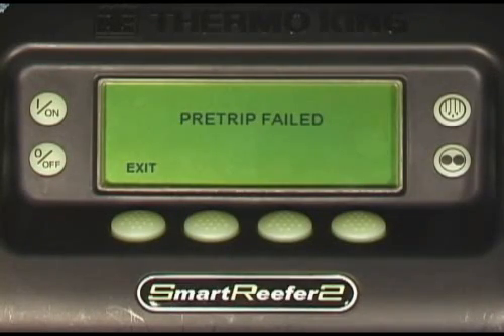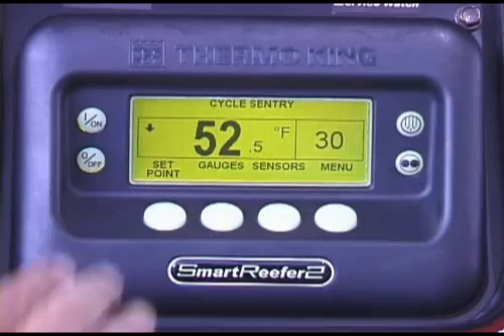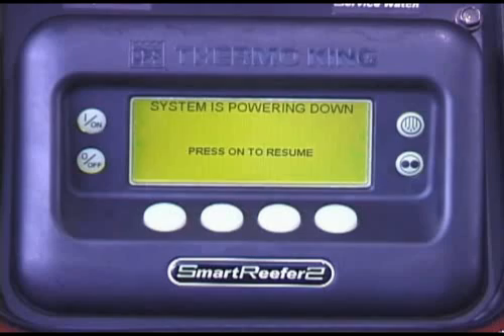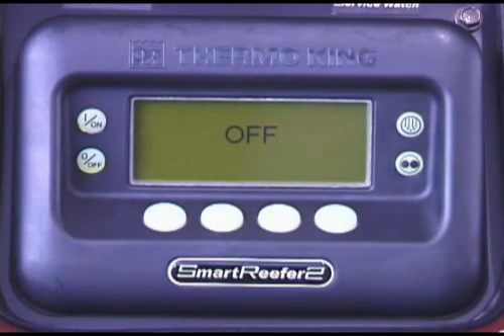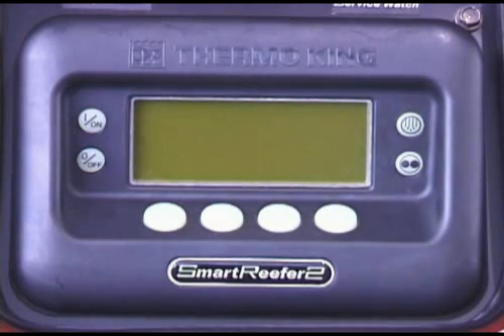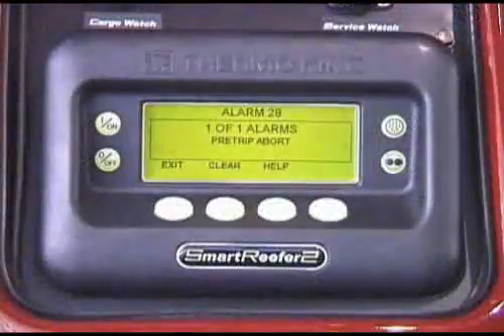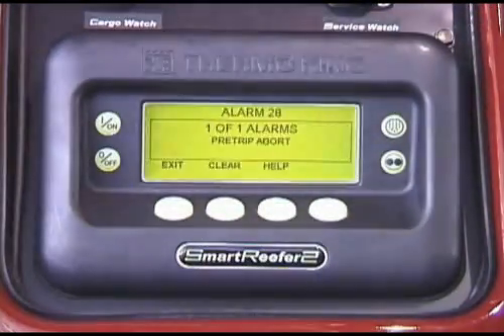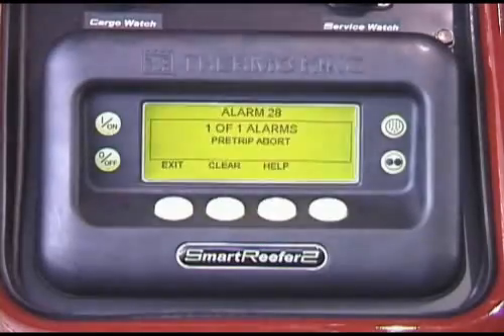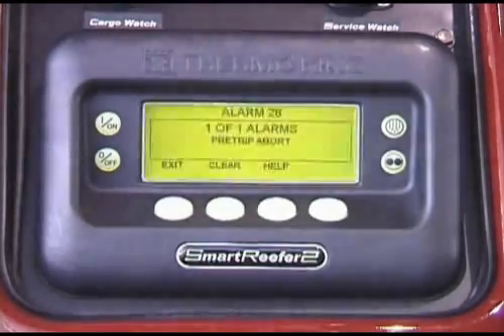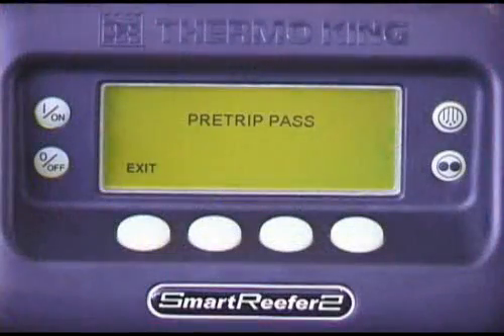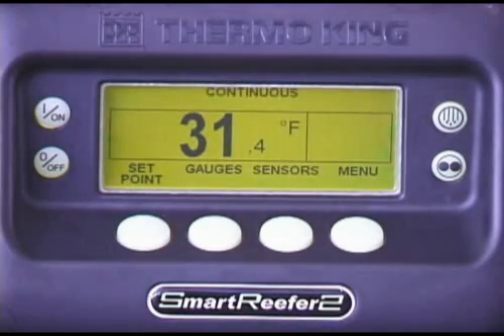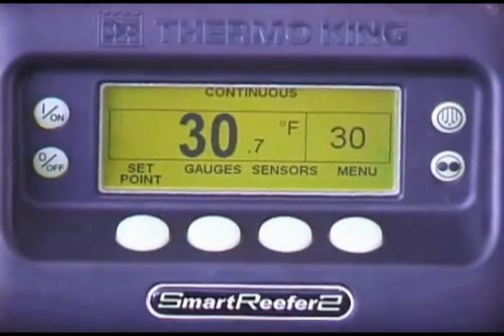If pre-trip check or pre-trip failed appears after the test, contact your ThermoKing dealer for assistance. Pre-trip can be terminated by turning the unit off. If this is done, however, the controller will register an alarm, or alarms, which must be cleared before the unit can be started again. This test may be run unattended.